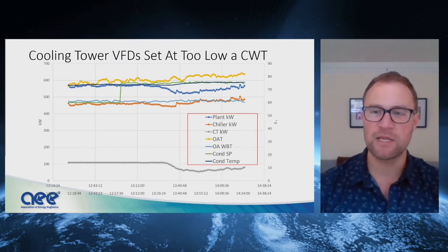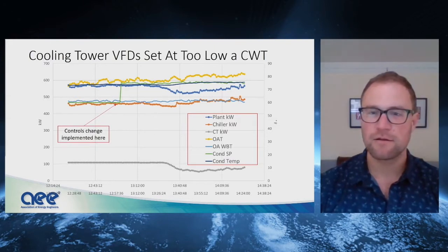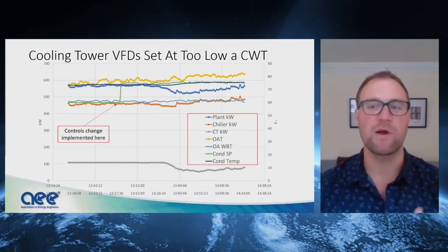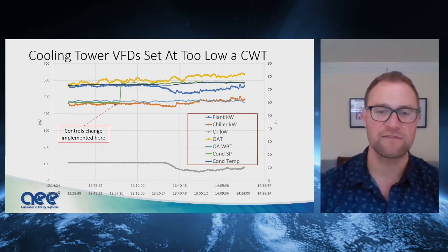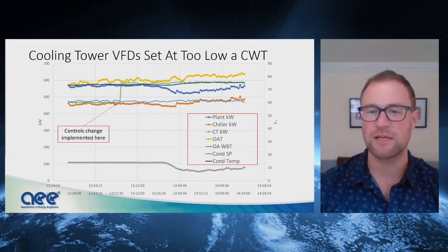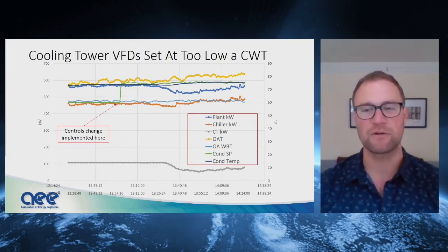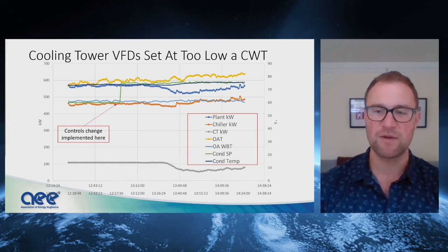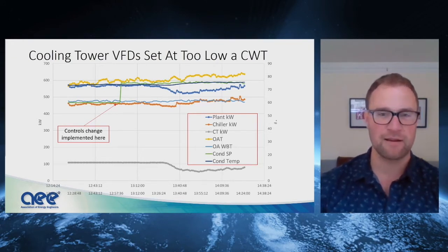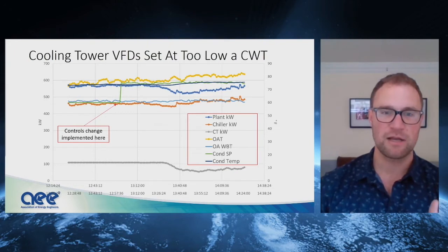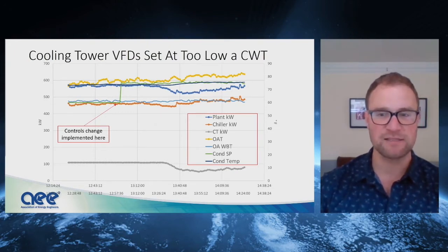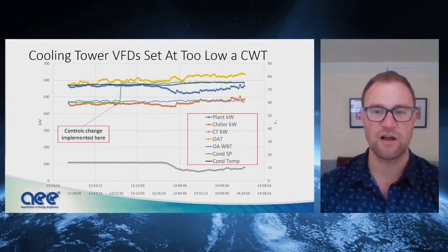And what you can see here is that we implemented the controls change to let the green line float with wet bulb, and you can see that it begins to track that blue line at an offset. It takes some time for the system to respond, but what this does is raise the condenser water temperature set point slightly, shifting a little bit of work back over to the chiller in orange. But that increase is more than offset by the dramatic reduction in fan kW in gray at the cooling tower, and that's because of the affinity laws, right? So it's a worthwhile trade-off.